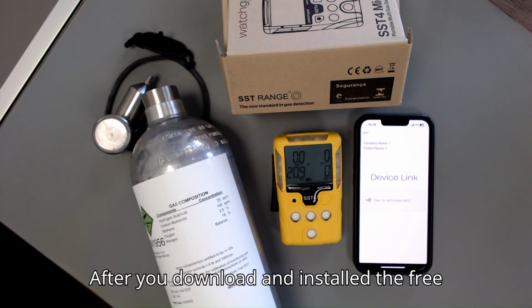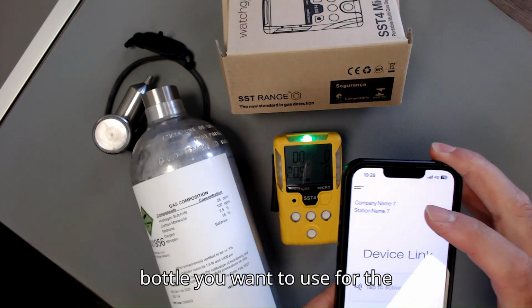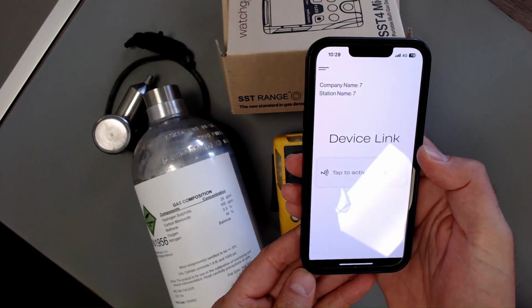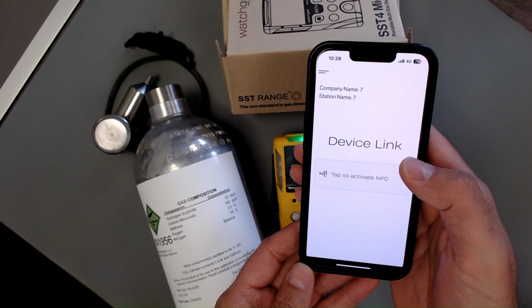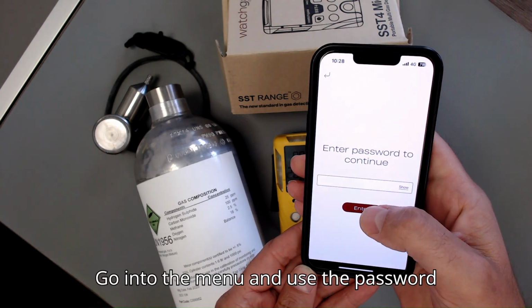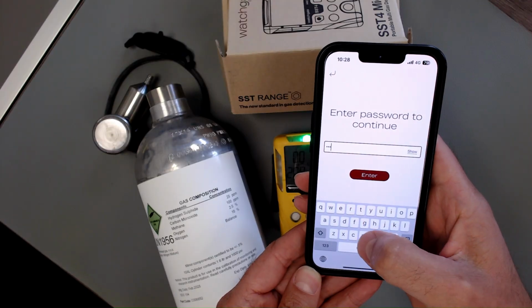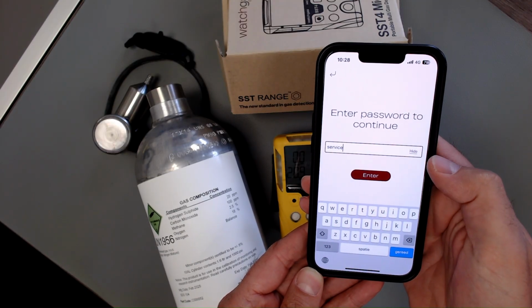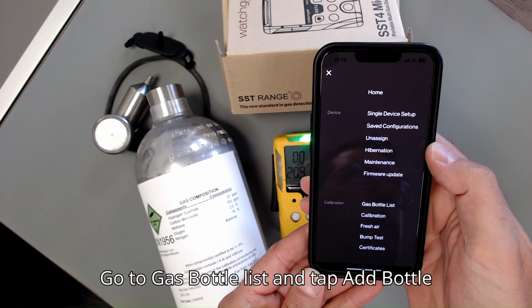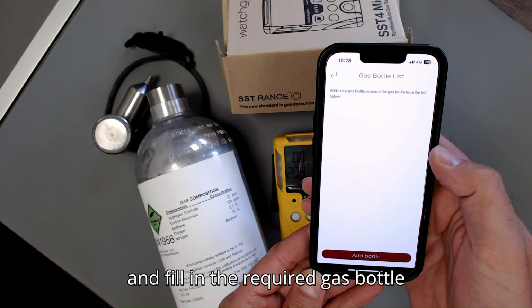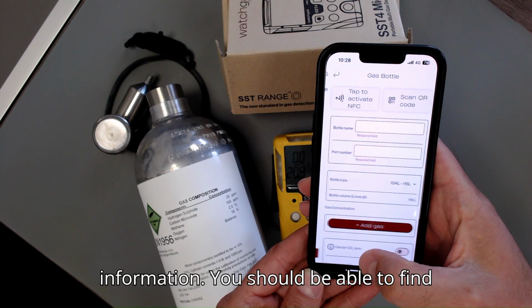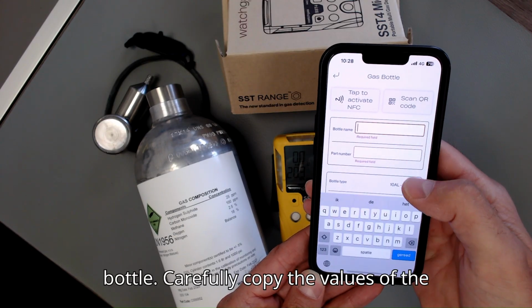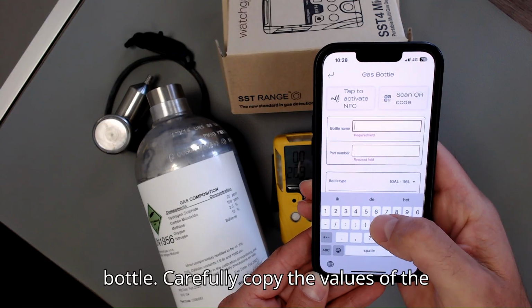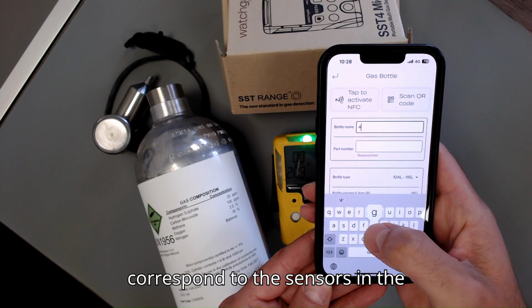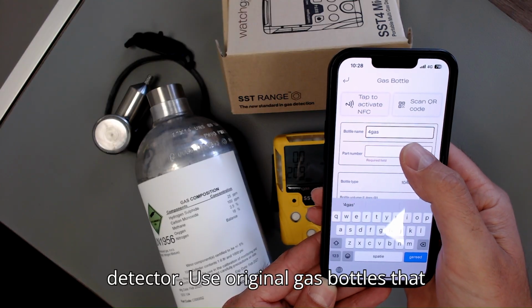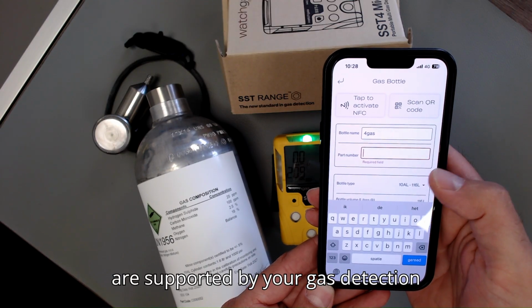After you download and install the free WatchGas app, you need to add the gas bottle you want to use for the calibration. Go into the menu and use the password service. Go to gas bottle list and tap Add Bottle and fill in the required gas bottle information. You should be able to find this information on the label of your gas bottle. Carefully copy the values of the gas bottle and be sure that these gases correspond to the sensors in the detector. Use original gas bottles that are supported by your gas detection supplier.